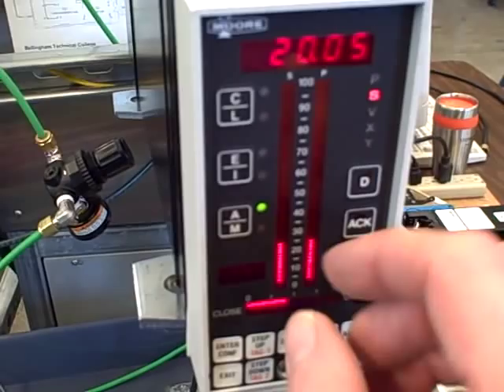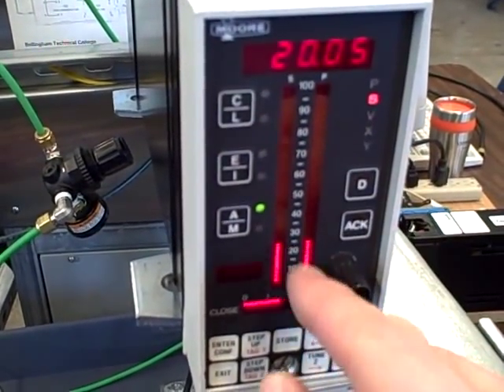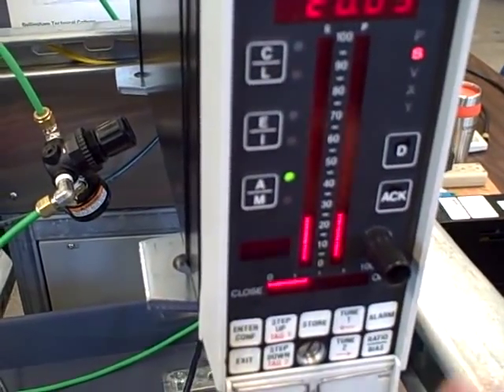What this means now is if I take my set point and adjust it up in the range, down the range, we see much more consistent response.